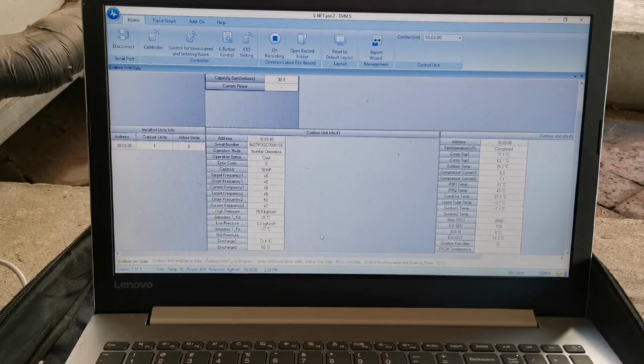That's the thing about these VRF systems, guys. Your manifold gauges mean nothing. If you don't have a service checker, you won't be able to properly diagnose these systems. So yeah, it's pointless I even try and put my gauges on, because it's not going to give me an accurate measurement of what's actually happening in the system. So it's really important that you are able to analyze the system data to see whether or not we've got an issue.